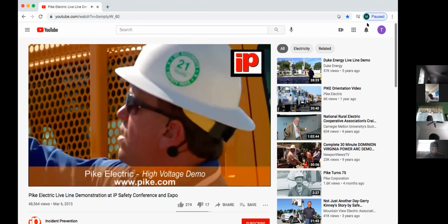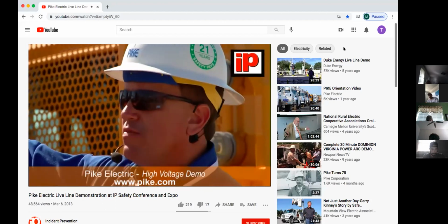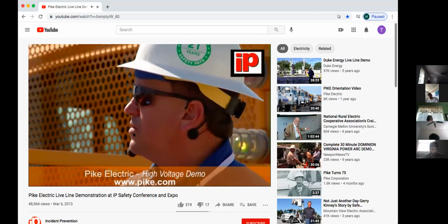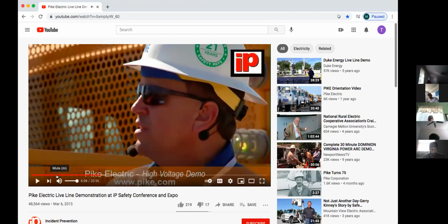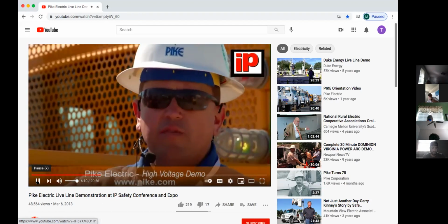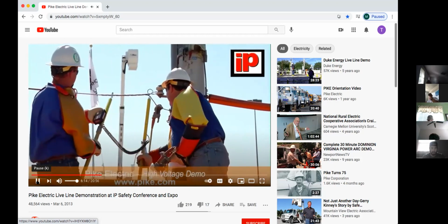Say something, Tariq. Taking the recloser off the line, they're going to establish a visible opening on the line. What happened? You're good. Keep going. Okay. And Joe's going to test the line for voltage, make sure there's no voltage on the line.